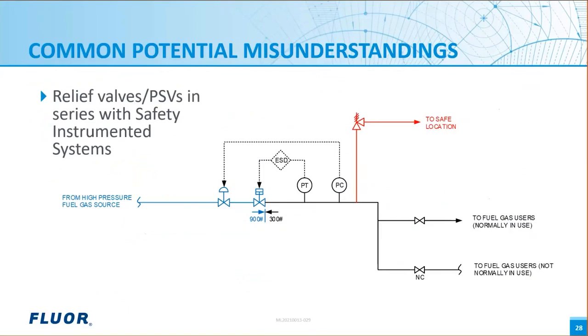scope, the scenario of concern was closure of that manual valve on the right, the upper valve, which would lead the system to be shut in, which could result in overpressure if you have gas coming from a high pressure source. So in this situation, it's tempting to say that if our safety instrumented system activates, the time that it takes to close is not too important because any excess material will be relieved from the system by the pressure relief valve. And that's a bad basis to choose because we need our protection layers to be independent layers of protection. So they have to act as a safeguard in their own right. So when we're doing our process safety time calculation, we can't take any credit for the pressure relief valve doing its job. So that's the first thing to look out for.